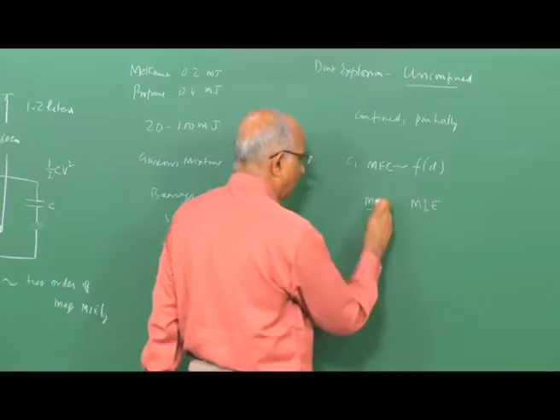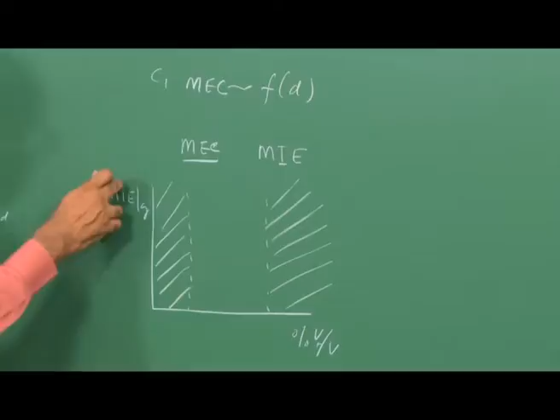vapor, or volume of fuel in the volume of the mixture as a percentage, against minimum ignition energy for a gas, and we found below some threshold value of the fuel in the volume of the mixture, the gas just does not ignite. We also said above a certain threshold value, well, the gas does not ignite. And when the gas does not ignite, what does it imply?